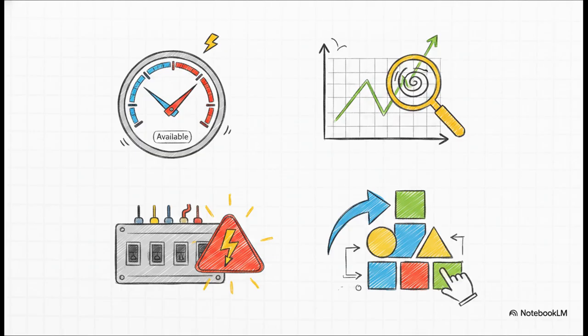So what exactly does this console let those operators do? By pulling in data from all over the facility, it acts like a digital sixth sense. It tracks exactly how much power is available versus how much is actually being consumed. It pinpoints peak loads, identifying exactly which racks or cooling systems are drawing the most juice. It finds hidden spare capacity, identifies if a breaker, a PDU, or a feed is at risk, measures overall energy efficiency, and crucially gives operators the hard data they need to know exactly when to shift, limit, or prioritize workloads.